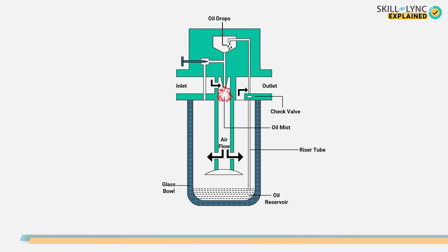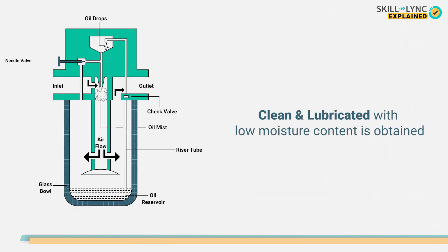The oil finally comes out as a spray and mixes with the air. The oil flow rate can be adjusted by a needle valve. Moreover, the larger oil particles in the air-oil mixture are removed as the air swirls around the central cylinder. Finally, clean and lubricated air with low moisture content is obtained at the outlet to be used in the system.